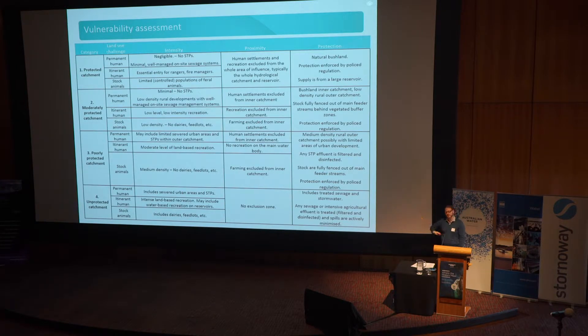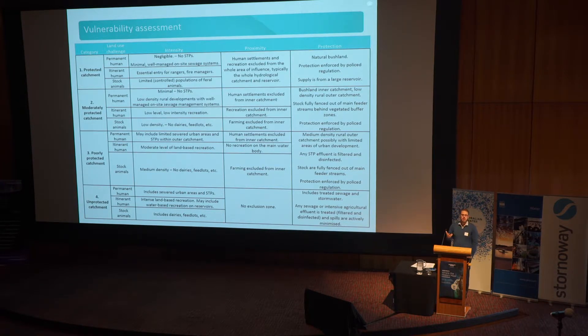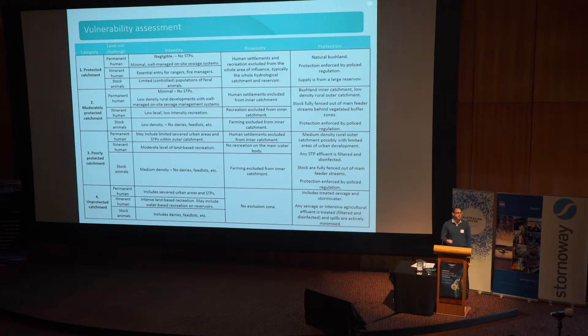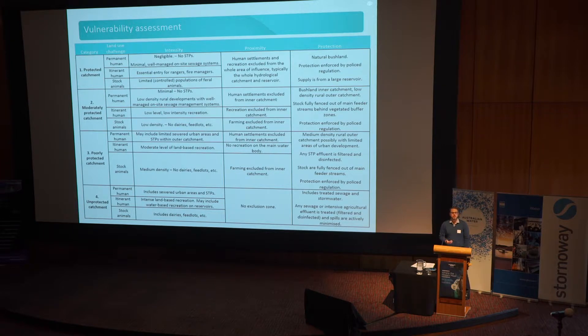This first phase of the methodology is essentially trying to characterize what activities in your catchments have potential sources of pathogens. The WSAA group put together a bin system — four categories or four different catchment types, from protected all the way to unprotected. A protected catchment has no human activity: no STPs, no on-site wastewater systems, no people recreating, no stock animals. An unprotected catchment has sewered areas, STP discharges, on-site wastewater systems, and stock, whether feedlots or dairies.